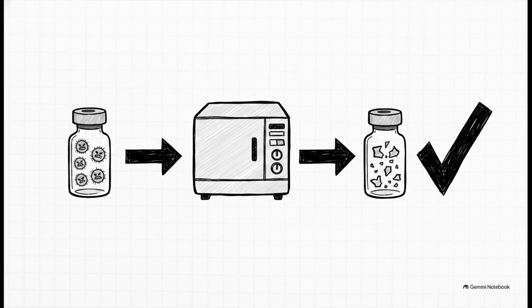But here's the real genius part. Having the technology just isn't enough. You have to prove it works every single day. Central processing teams are constantly monitoring these machines using biological indicators. They literally put incredibly tough live bacterial spores right into the sterilizer alongside the equipment. If the machine successfully kills off those hyper-resistant spores, the team knows for an absolute fact that the cycle is lethal enough to handle any pathogens on the surgical instruments.